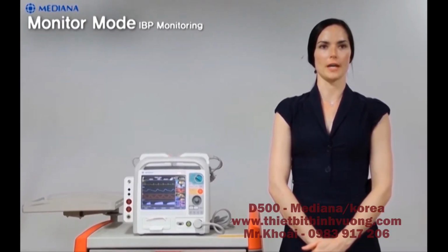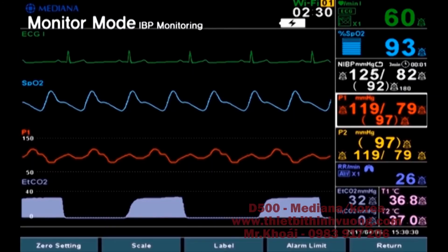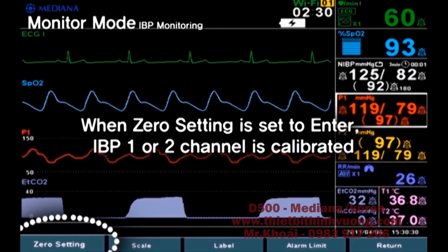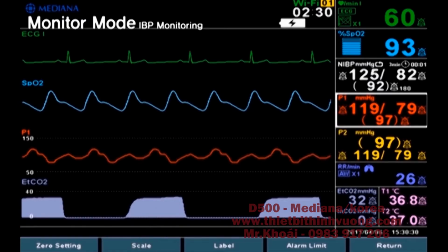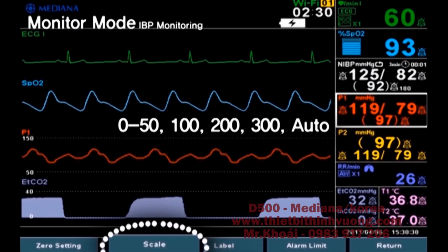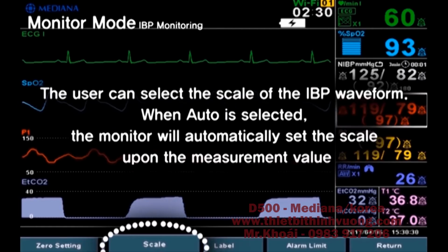Now for a look at the IBP menu. Number 1. Zero setting. When zero setting is set to enter, the IBP 1 or 2 channel is calibrated. Number 2. Scale. 0 to 50, 100, 200, 300, and auto. The user can select the scale of the IBP waveform. When auto is selected, the monitor will automatically set the scale based on the measurement value.